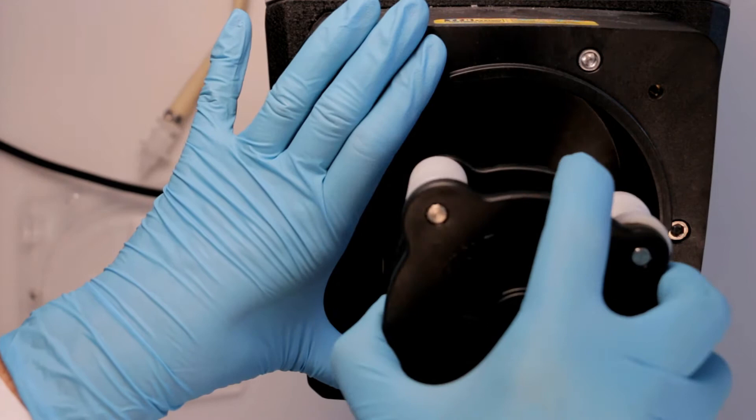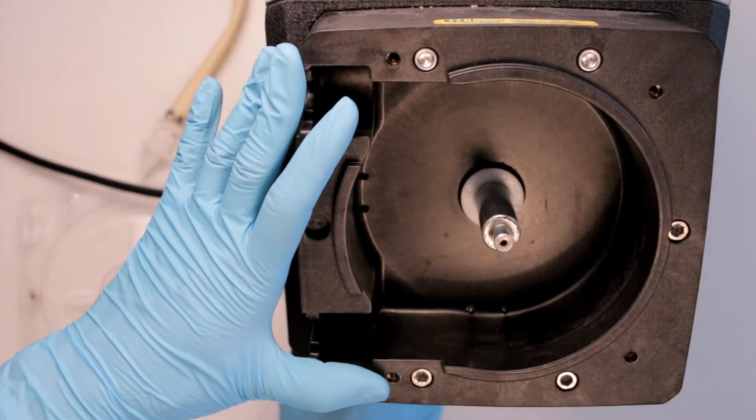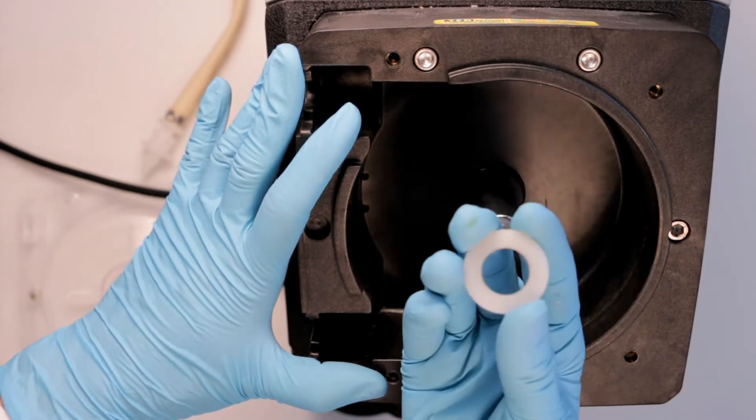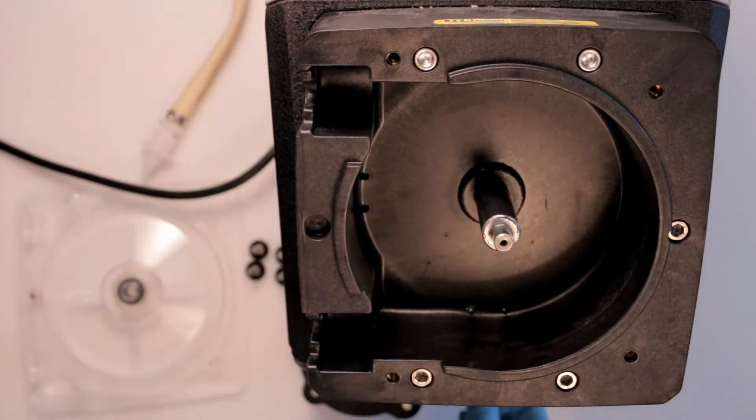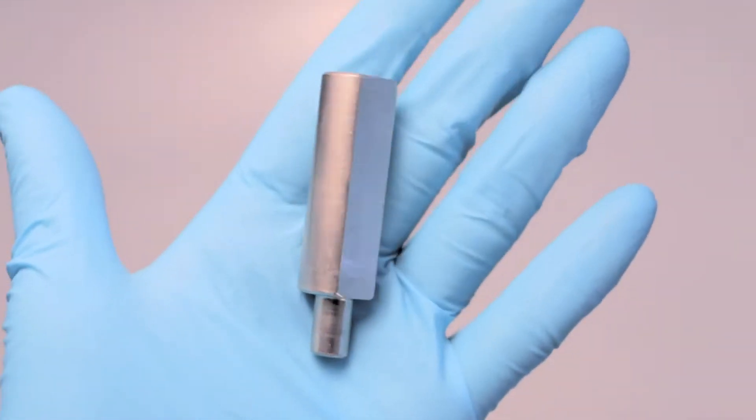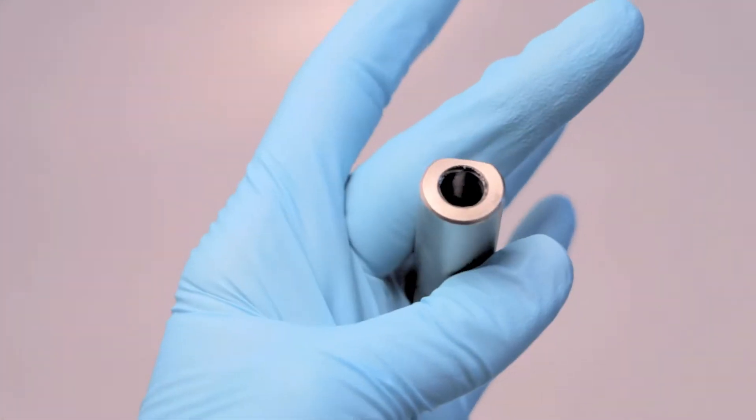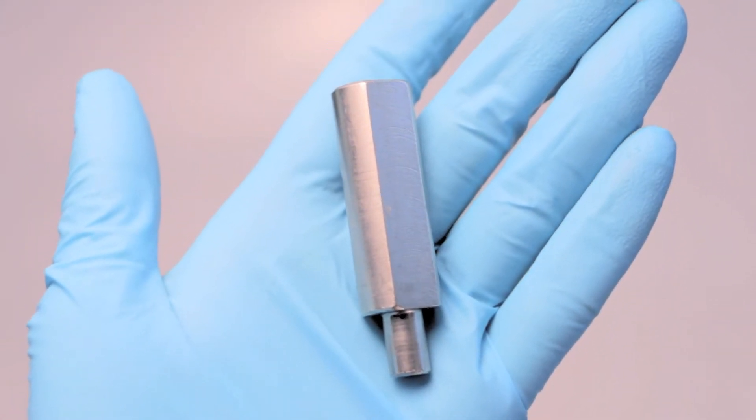Slide the roller assembly from the motor shaft. Take note of the white spacers. This pump only has one in the back. If you're working with the large A4 and M4 pumps, you'll notice the shaft extensions still inside the roller assembly when it's pulled from the pump head. You can knock this out with a screwdriver and a mallet.